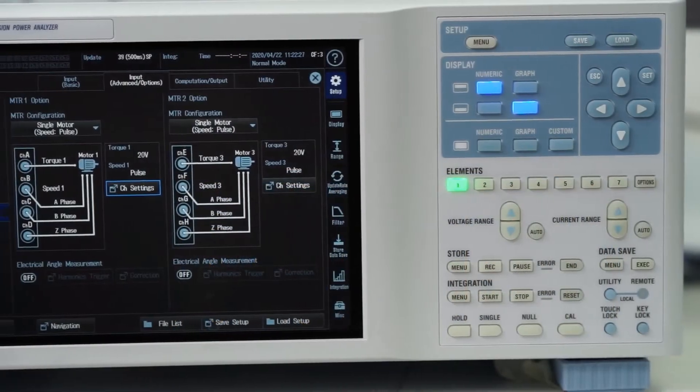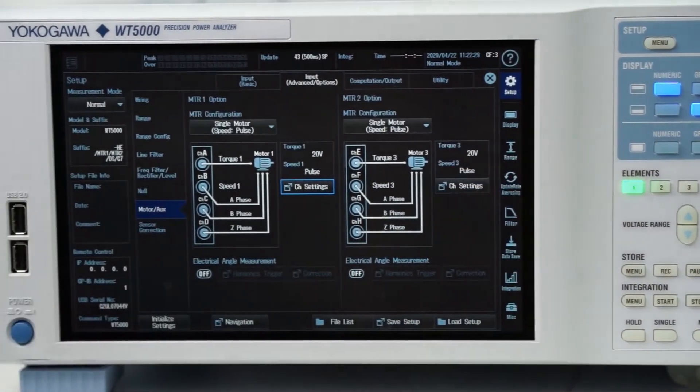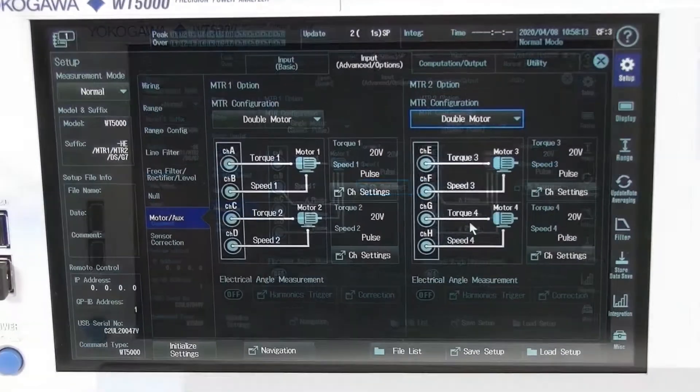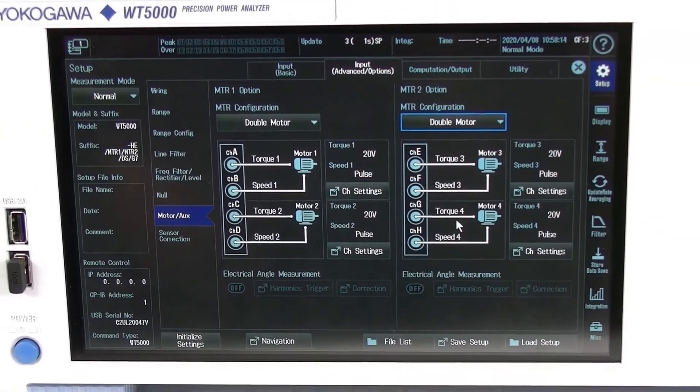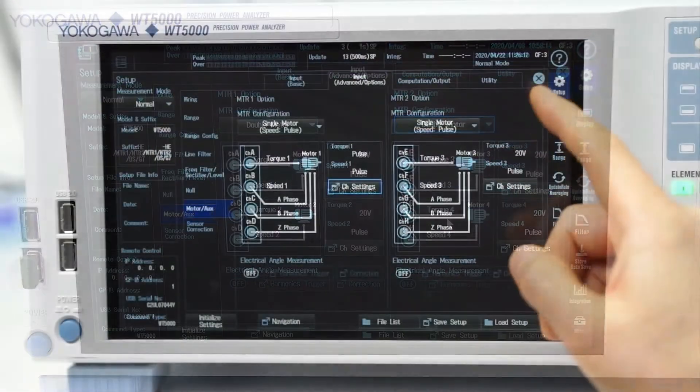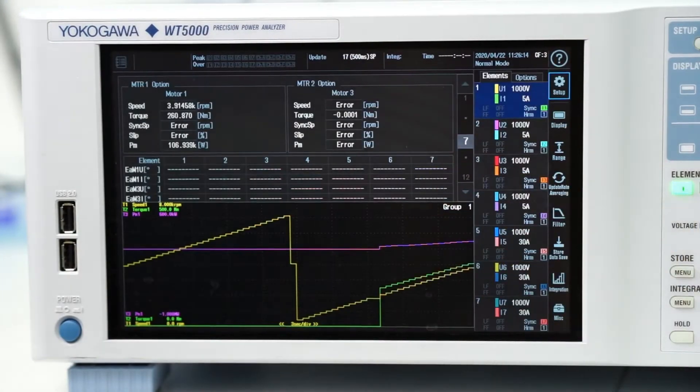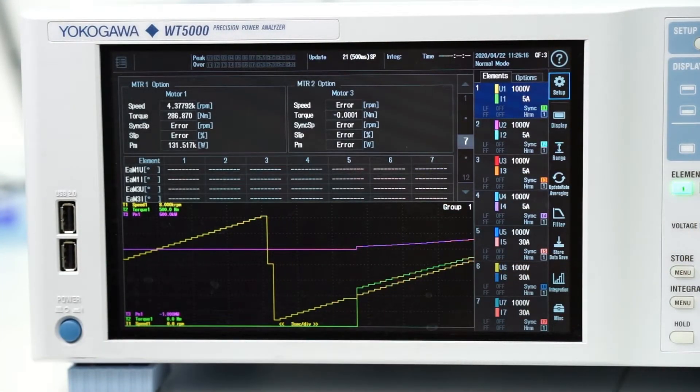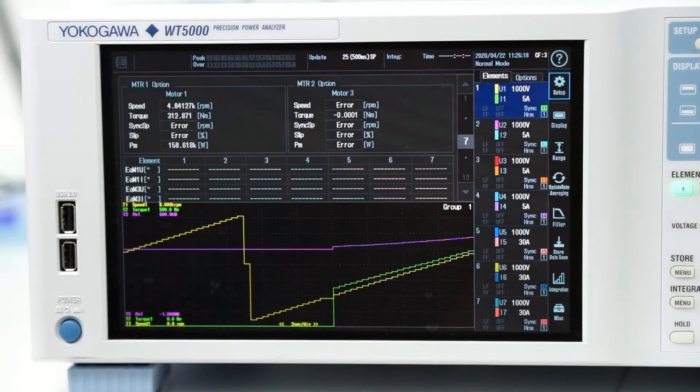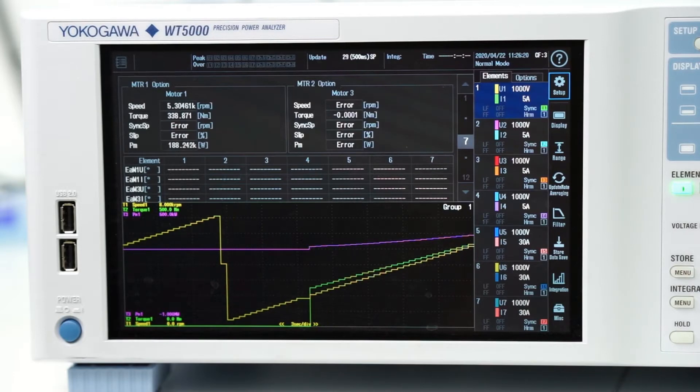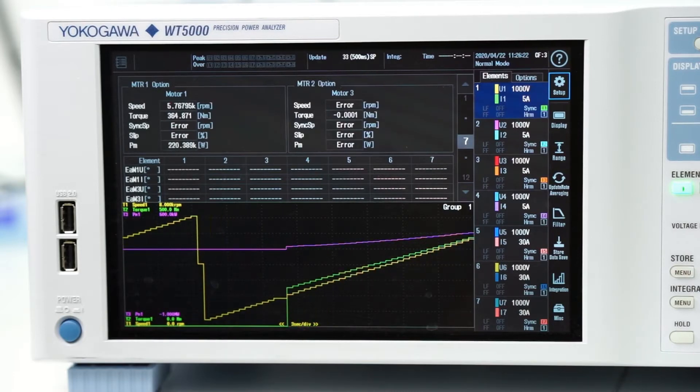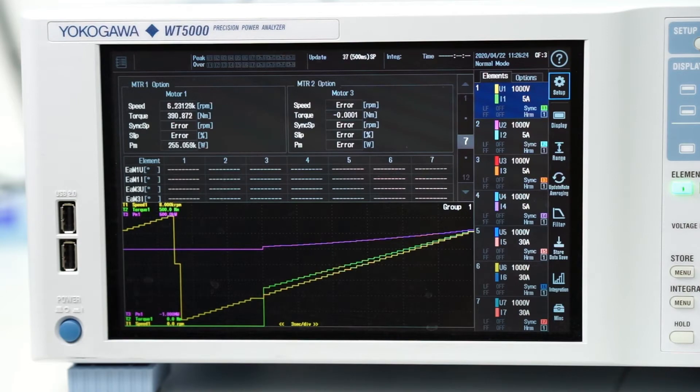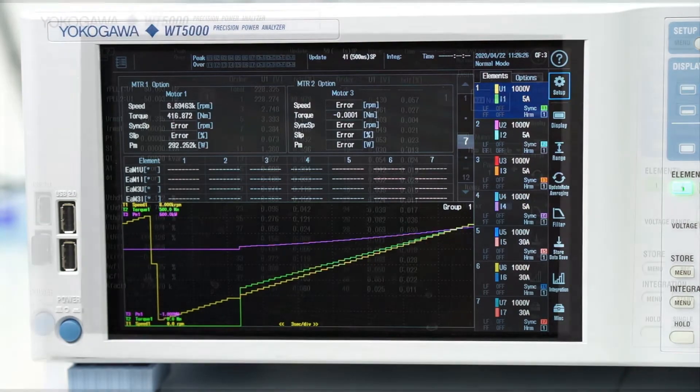It also provides dedicated motor measurement functions which can be configured to measure as many as four separate motors simultaneously. The instrument can acquire readings of rotation speed and direction, synchronous speed, slip, torque, mechanical power, electrical angle and motor efficiency from the outputs of torque or rotation sensors.